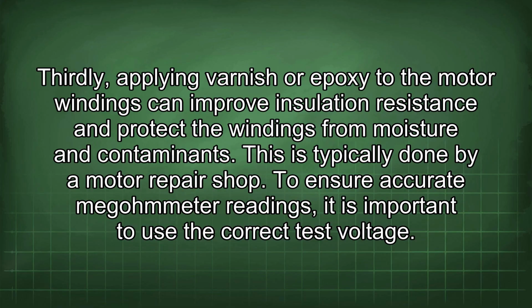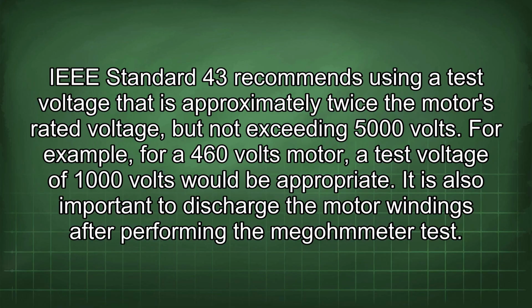To ensure accurate megohmmeter readings, it is important to use the correct test voltage. IEEE Standard 43 recommends using a test voltage that is approximately twice the motor's rated voltage, but not exceeding 5000 volts.